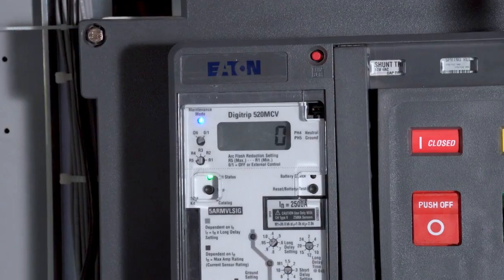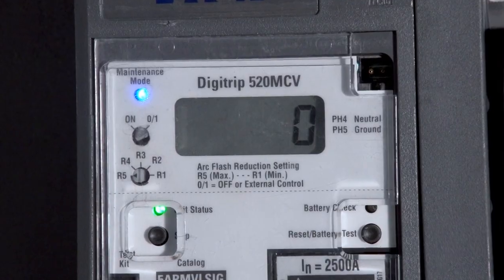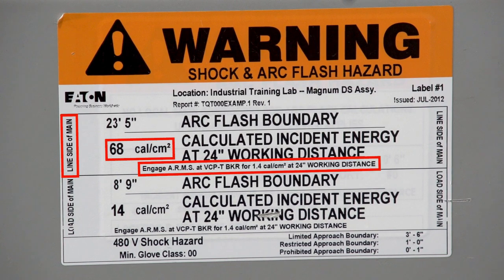Using an ARMS setting on the medium voltage breaker, it will trip without delay during a fault condition. This arc flash label indicates that the arc flash energy at the line side of the breaker is normally 68 calories. The ARMS solution significantly reduces the arc flash energy to 1.4 calories during maintenance conditions.